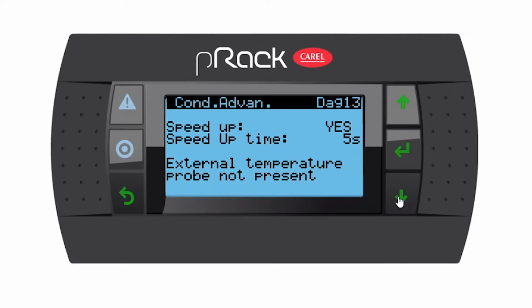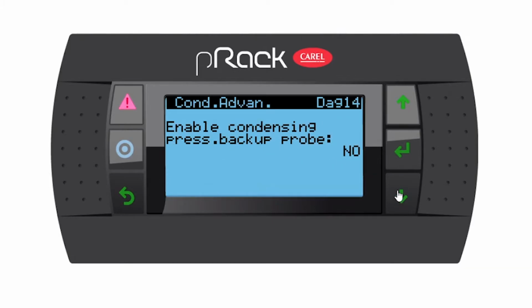Go down. Speed up, yes. Speed up time 5 seconds. External probe not present. Let's leave this as is and go down. Enable condensing pressure backup probe. So here you have the option to say yes if you want to install a secondary probe, condensing probe. And when the first one fails for any reason, the controller will automatically look at the second one and still regulate. But I'm going to leave this as no and go down.